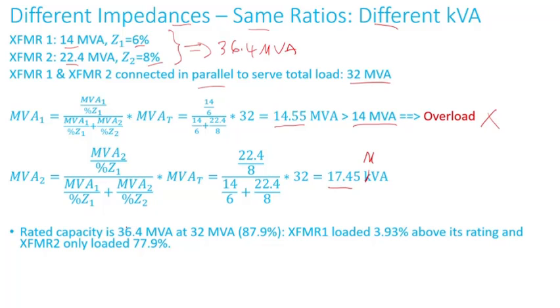The total capability of this substation — transformer one plus transformer two — is 36.4 MVA. The load is only 87.9% of the total capability, yet I'm already overloading transformer one by 3.93% above its rating.